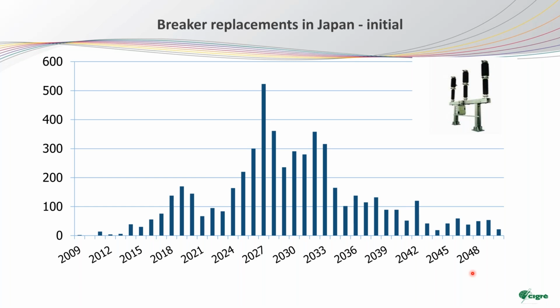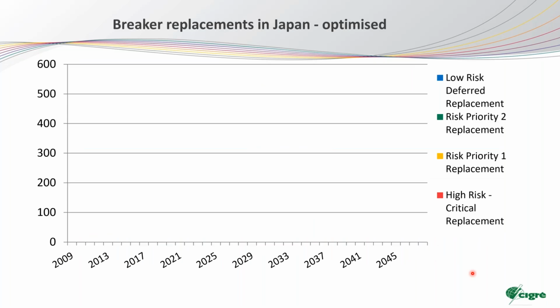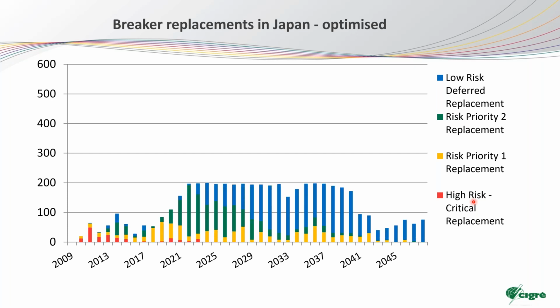So they followed a different approach. In order to replace the old circuit breakers in Japan, they decided to divide these circuit breakers into a number of categories based on the risk. There are circuit breakers with low risk, and the replacement was deferred. There are circuit breakers with risk priority 2 or risk priority 1, and the replacement is going to be prioritized. And the high-risk circuit breakers will require replacement as soon as possible. Of course, the calculation of the risk is based on the available data, but when they followed this approach, they were able to have a smooth replacement plan, as you can see here.